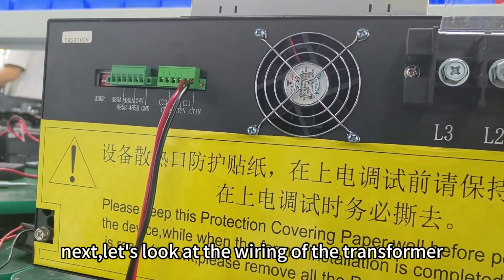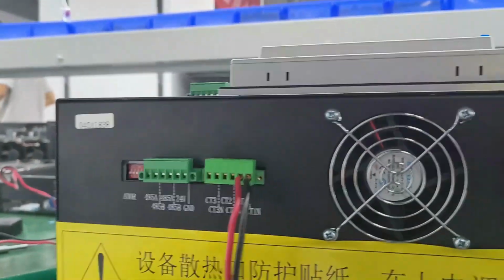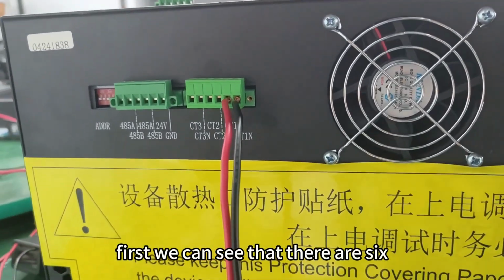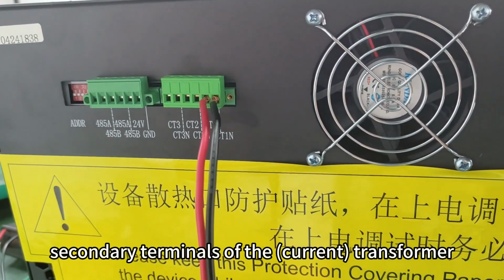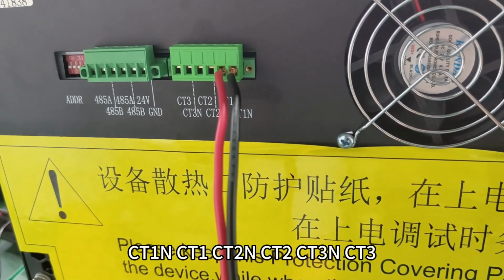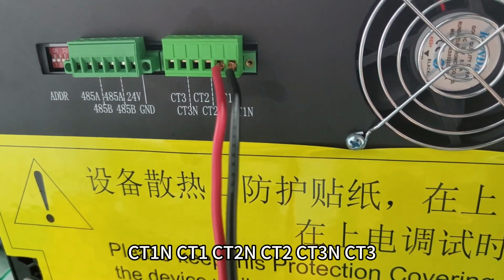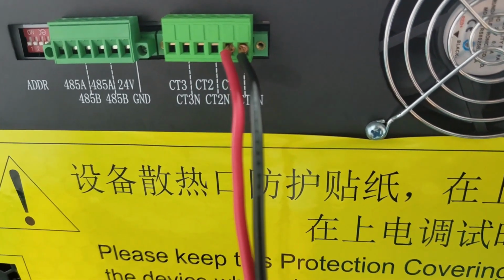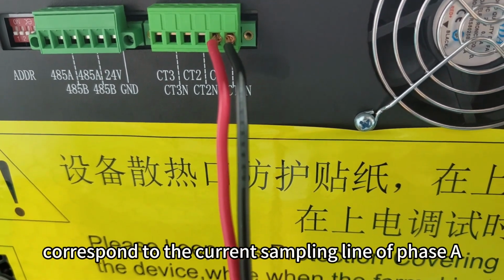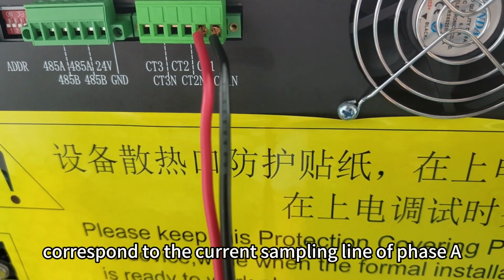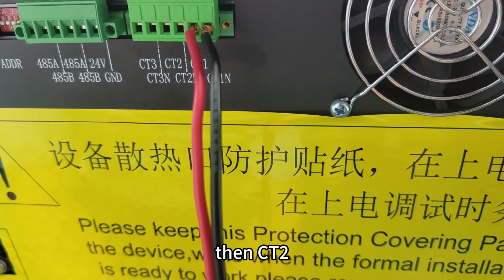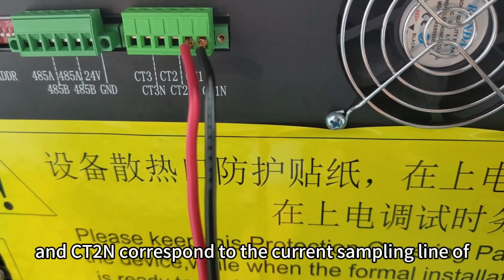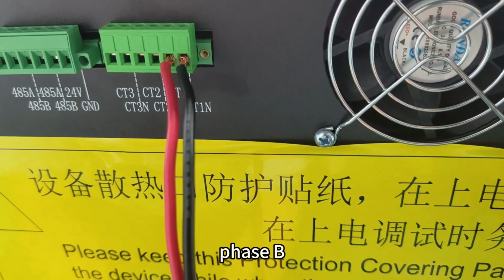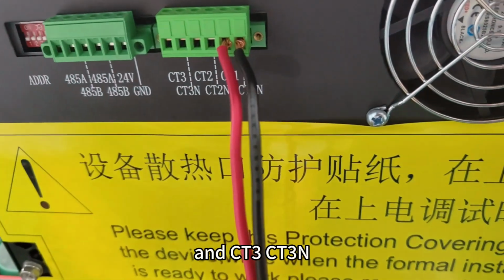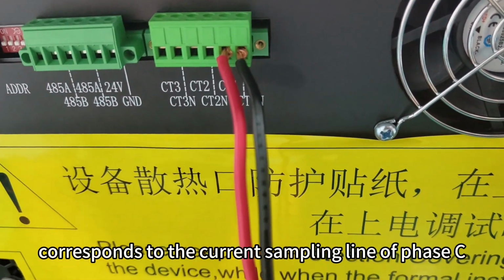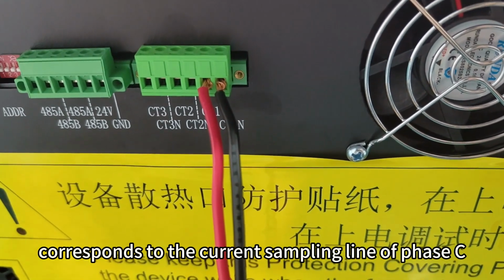Next, let's look at the wiring of the transformer. First, we can see that there are 6 secondary terminals of the transformer: CT1N, CT1, CT2N, CT2, CT3N, CT3. CT1 and CT1N correspond to the current sampling line of phase A, then CT2 and CT2N correspond to the current sampling line of phase B, and CT3 and CT3N correspond to the current sampling line of phase C.